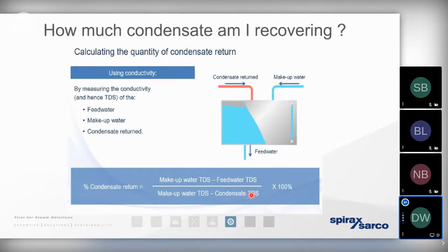So a client may say, yes, we're aware of the benefits of recovering condensate, but how much condensate am I actually recovering? How efficient is my steam system actually working? And the good news is that the vast majority of steam-using sites will already be calculating how much condensate they're recovering, although they may be completely unaware of it. And that's because boiler guidance, BG01 and BG03, obliges us to measure or monitor the water quality on a daily basis in three different areas of the energy center.